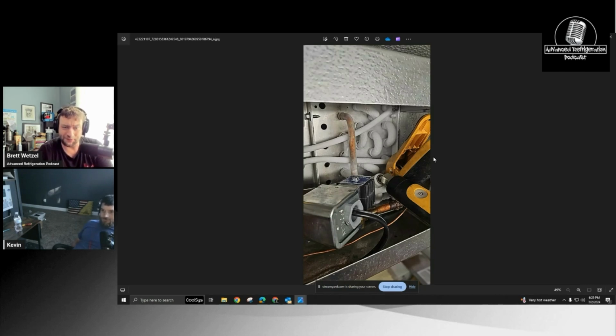And I'm like, what the hell? It's still bad. But then if you look at the refrigeration schedule, it'll say, okay, it's a 10,000 BTU coil, but it actually has a 30,000 BTU expansion valve in there. So that's where this comes into play.